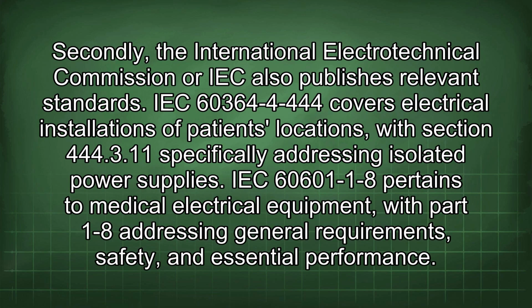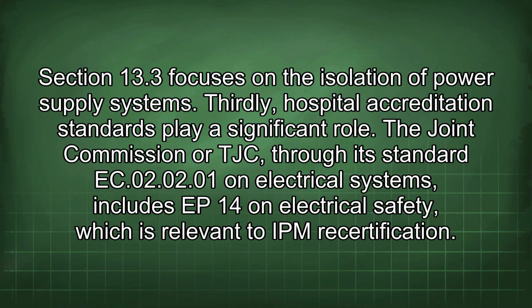Secondly, the International Electrotechnical Commission, or IEC, also publishes relevant standards. IEC 60364-4-444 covers electrical installations of patients' locations, with Section 444.311 specifically addressing isolated power supplies. IEC 60601-1-8 pertains to medical electrical equipment, with Part 1-8 addressing general requirements, safety, and essential performance. Section 13.3 focuses on the isolation of power supply systems.